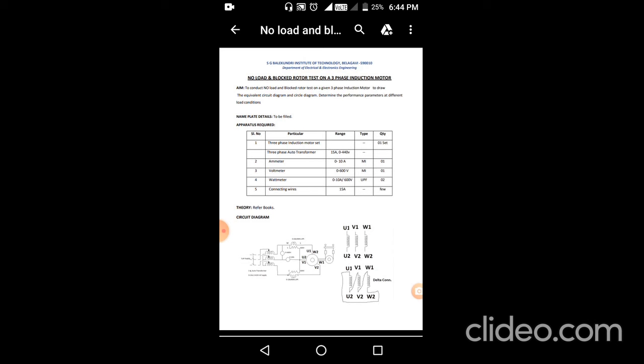Some apparatus is required to conduct the no load and block rotor tests, as shown in the table. We need one three-phase induction motor, one three-phase auto transformer, one ammeter, one voltmeter, two wattmeters, and some connecting wires to make the connections. The equipment used should be selected as per the specification and range mentioned in the apparatus table.